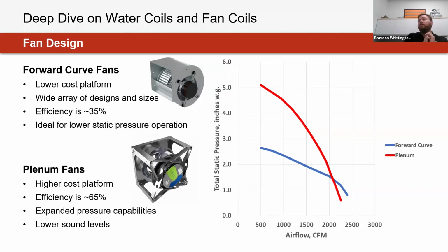And then once we start to get into the more specialized zone, starting to get into 4 inches of static or even higher for feeding into systems, that's when you might start to utilize plenum fans. The reason for that is that they do have a higher cost platform associated with them, but it expands the overall pressure capabilities of how much it can handle. So that's how large a space it can really serve, and also the number of coils that we can add to this product, which, as we'll learn in a little bit, can also be beneficial from a sound level perspective.